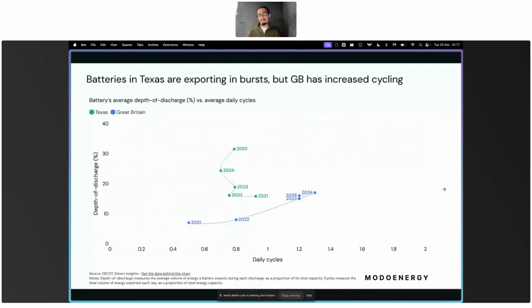We believe that this increasing depth of discharge in the Texas battery market, and this relatively high average value, is one of the reasons why batteries may be degrading faster than expected. There are a few activities that increase degradation rates, as Tristan will also point out, and depth of discharge is one of them. Operating at extreme ends of the state of charge and sustaining those energy levels tends to result in faster degradation.